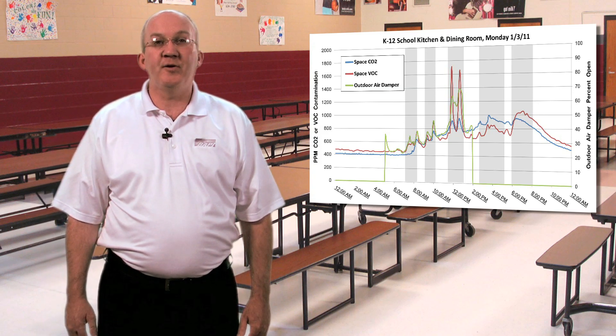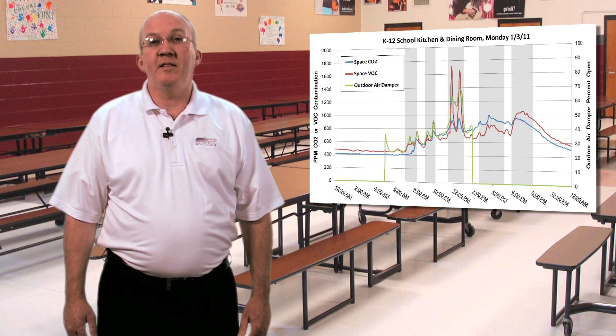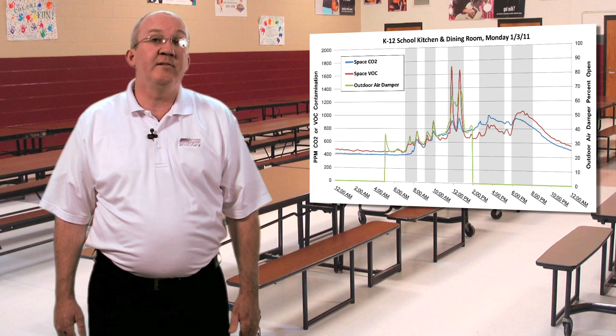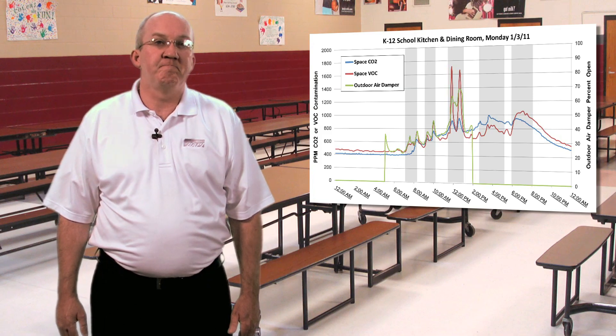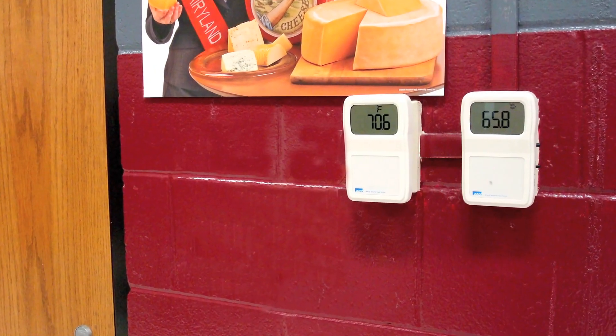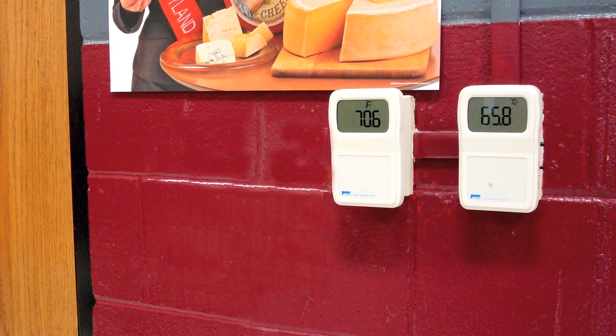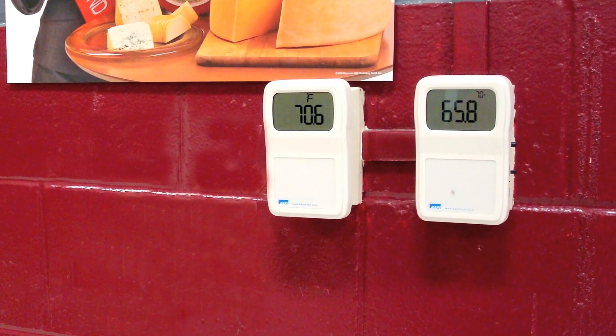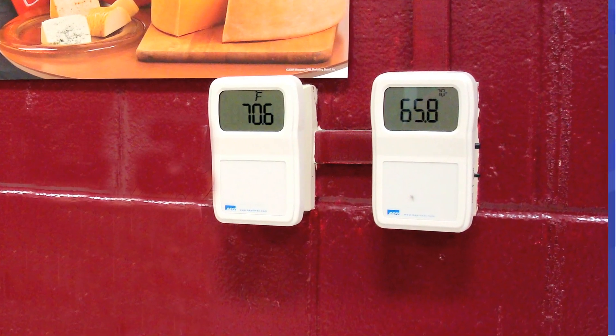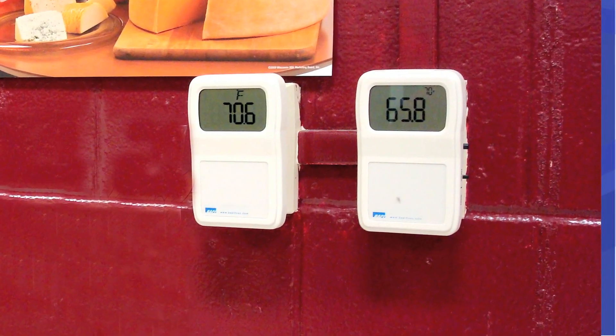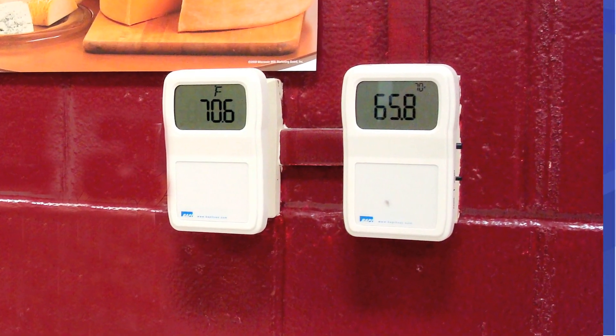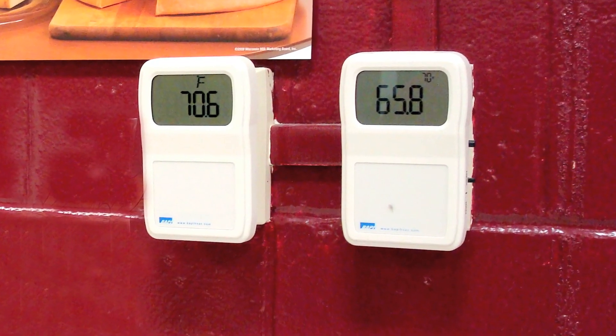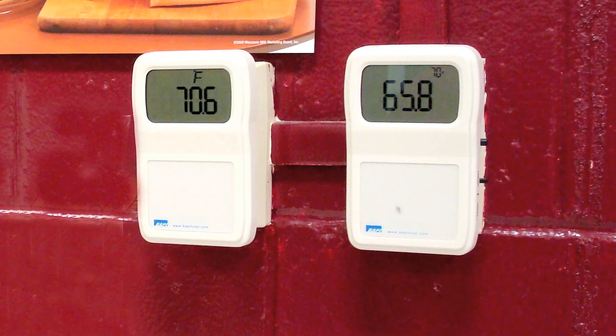The space is also used for athletic practices, exercise classes, and occasional adult meetings in the evening. The VOC and CO2 sensors are located next to each other in the dining room near the kitchen entrance. The open percentage of the outdoor air damper for this area is controlled by the VOC sensor output through a PID control loop.